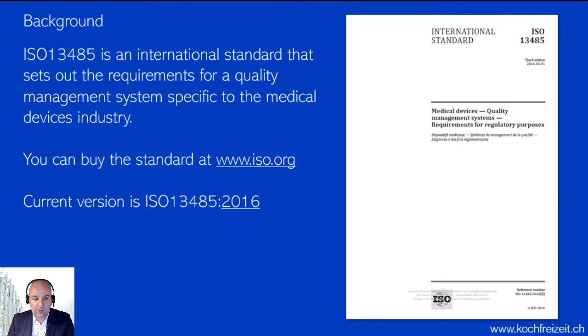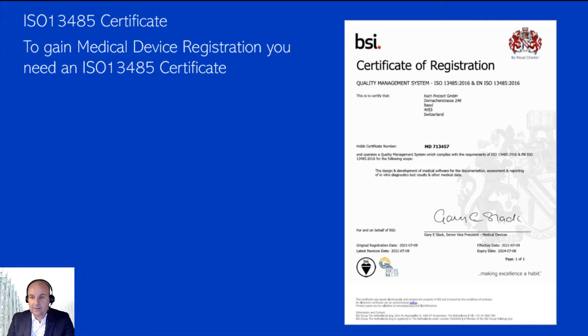And if you're committed to starting your project, you can go to iso.org and purchase this standard. The current version is actually the 2016 version. So they generally keep the old ones there that you can purchase, but make sure you get the right version. And this is what you're aiming for to gain registration of your device in a market. So what I mean by that is FDA registration, CE marking, etc.